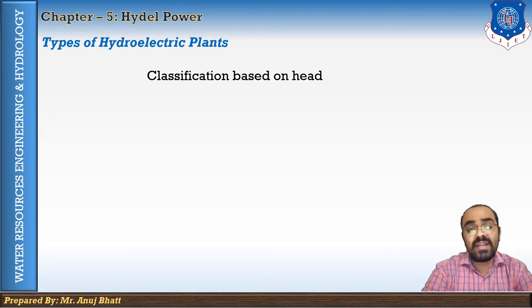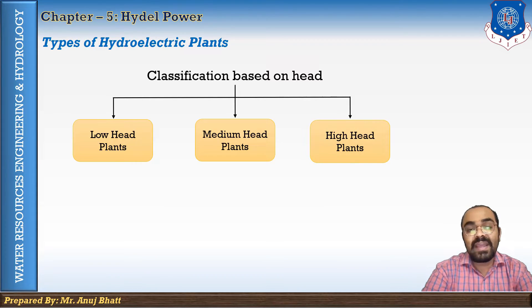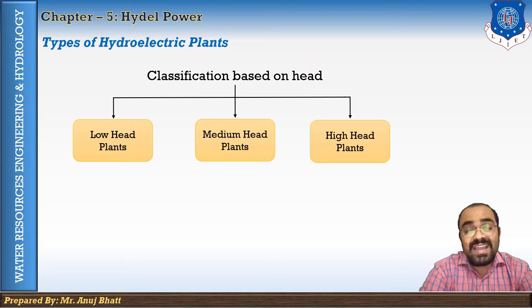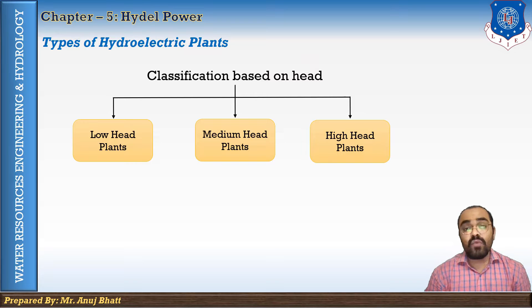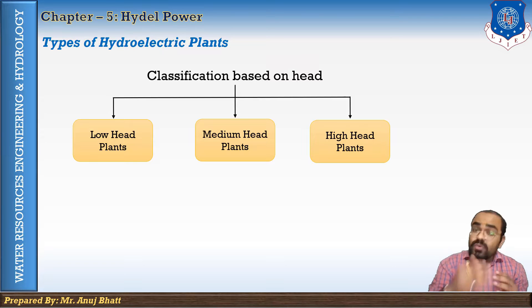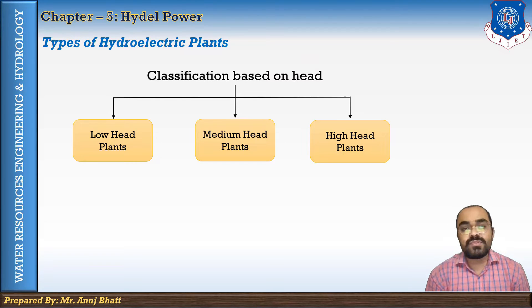The next classification is based on head. There are three categories: low head plants, medium head plants, and high head plants. A low head plant uses a head of less than 15 meters. It is essentially a runoff river scheme where a weir or barrage is constructed to raise the water level. The powerhouse may be constructed in continuation with the barrage.